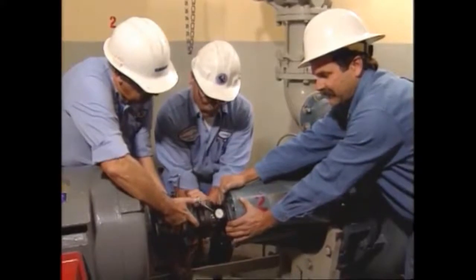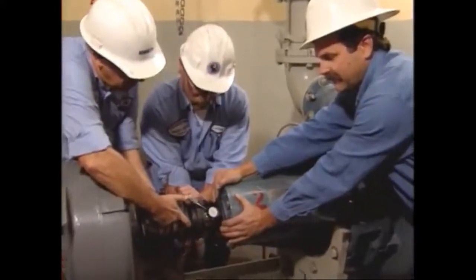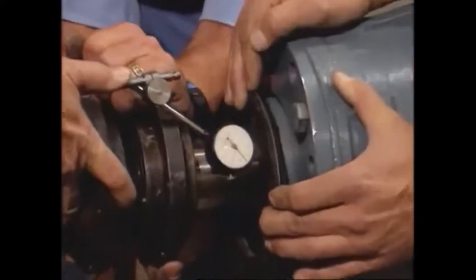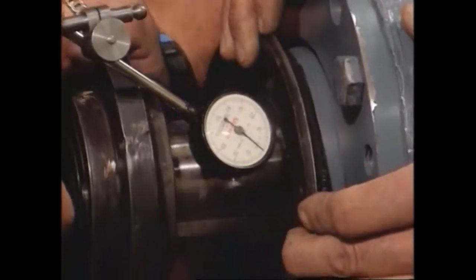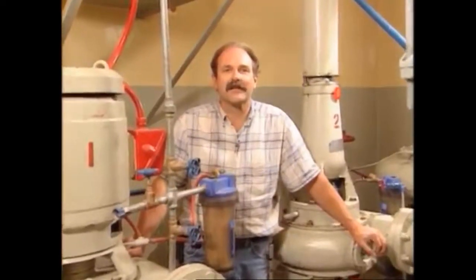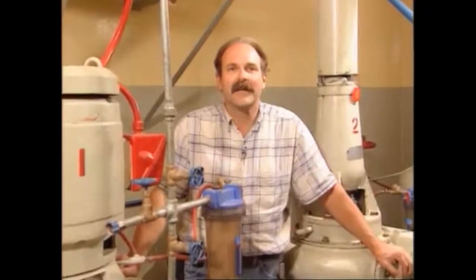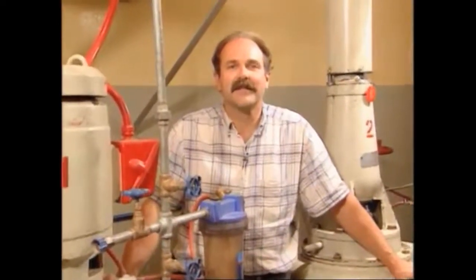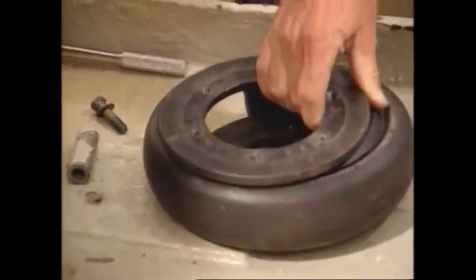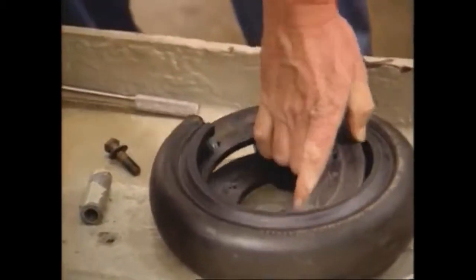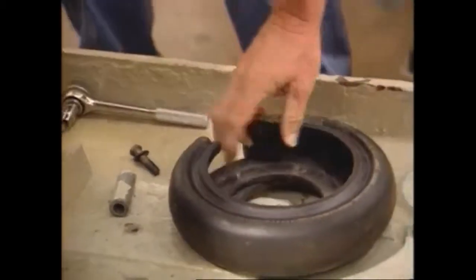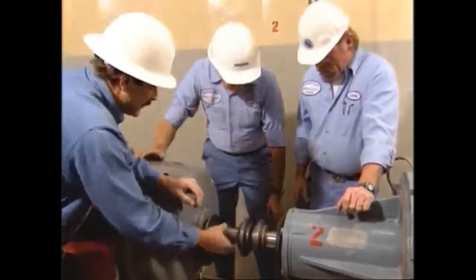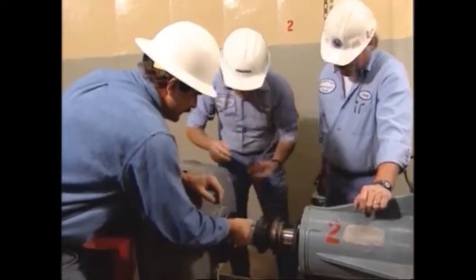Misalignment of the pump and the motor or any two pieces of rotating equipment can seriously damage the equipment and shorten the life of both the pump and the motor. Misalignment can cause excessive bearing loading and shaft bending. This could lead to early bearing failure and also excessive vibration and damage to the shaft. Remember that the purpose of the coupling is to transmit power, and unless the coupling is of special design, it is not to be used to compensate for misalignment between the motor and the pump.